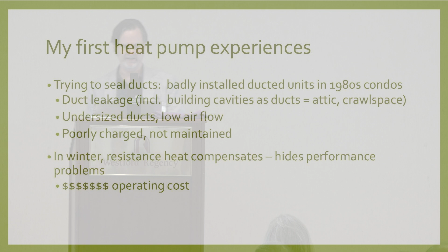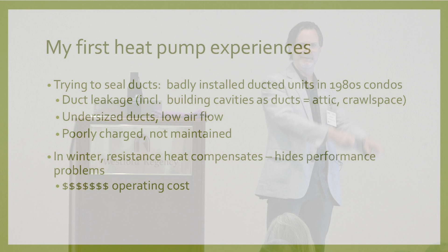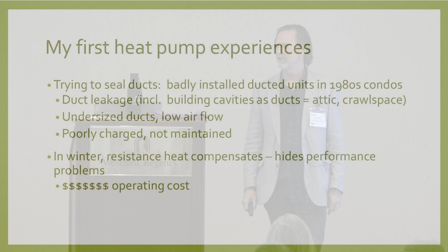All we really focused on at first was just sealing the ducts, because we were hearing about how important making ducts airtight would be. Some of these were terrible. They would use building cavities as ducts, like the fireplace and chimney chase was the pathway from the return plenum to the second floor return grills, but it also was connected to the vented cathedral ceilings. So all of the return air that made it into those units was coming basically from outdoors.